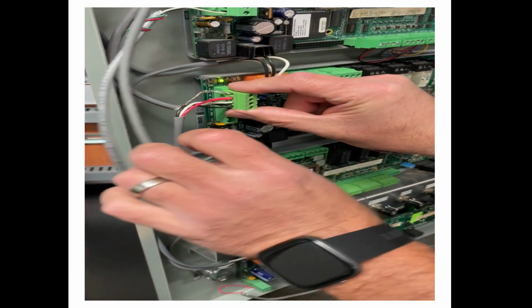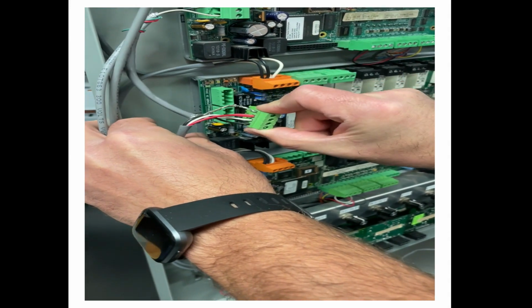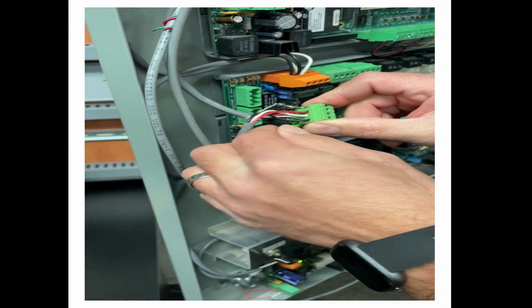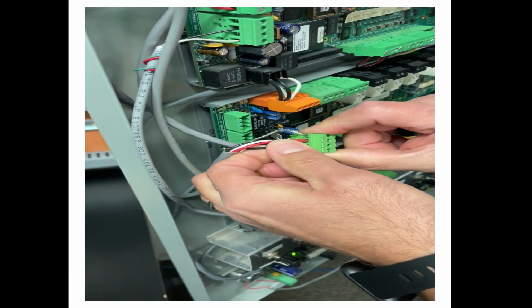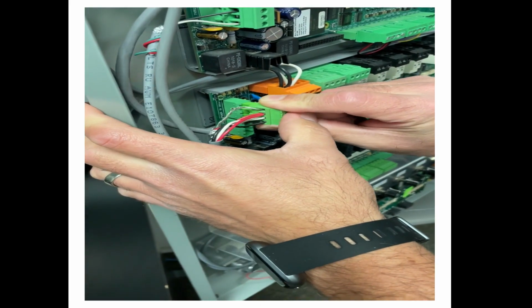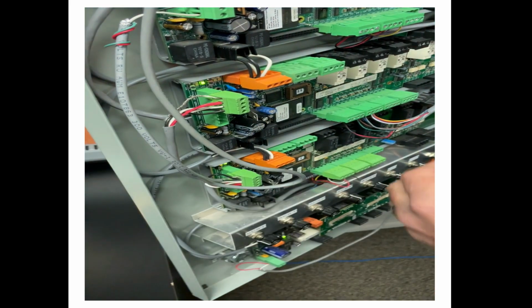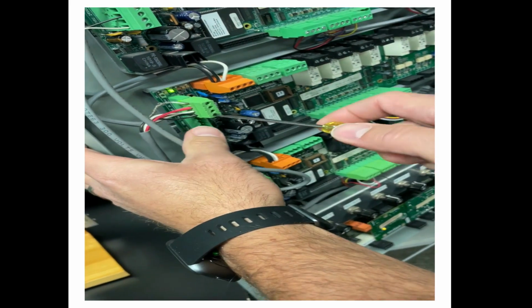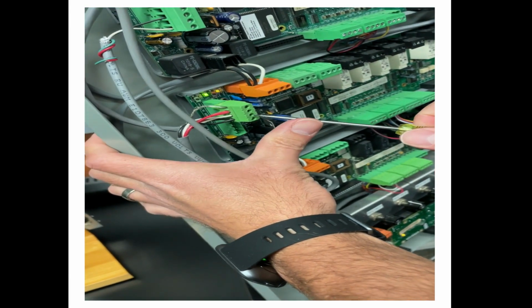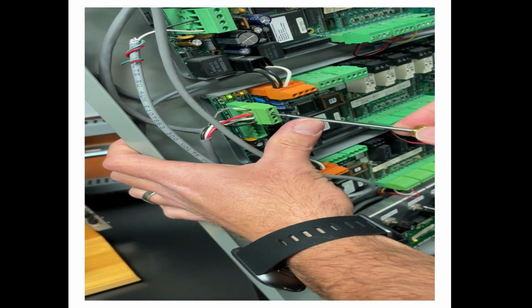Next, we will check the power supply to the MT500 board. Remove the green plug. Check that the wires are connected properly. Also look for any frayed wires or strands. Then take a control screwdriver and make sure the lugs are tightened properly.